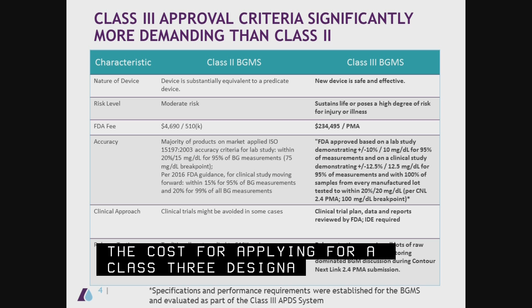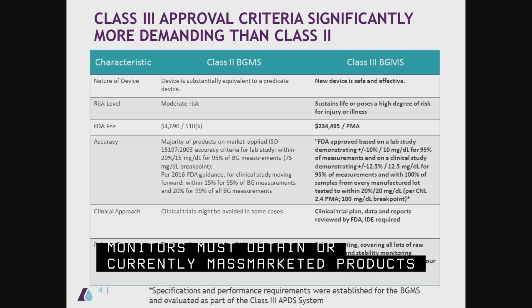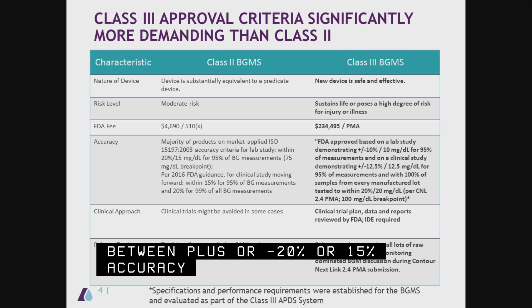But most importantly, for blood glucose monitoring, the requirements that need to be met with respect to accuracy, quality, and consistency are also much greater and must be demonstrated. The details are outlined in here, but essentially, while currently mass-marketed blood glucose monitors obtain somewhere between plus or minus 20% or plus or minus 15% accuracy to a lab reference in the majority of situations, the Class 3 BGM for use with an artificial pancreas system must consistently deliver plus or minus 10% accuracy.